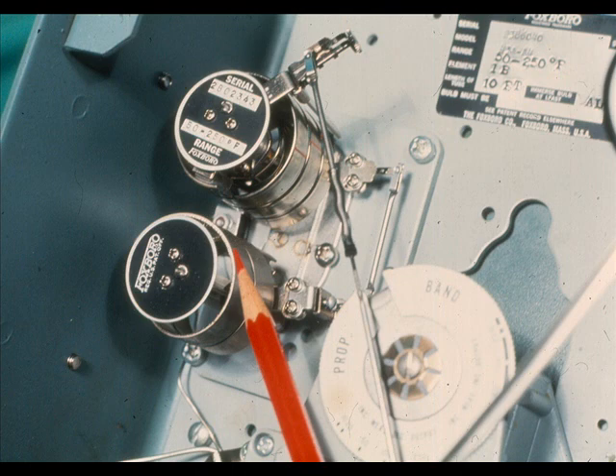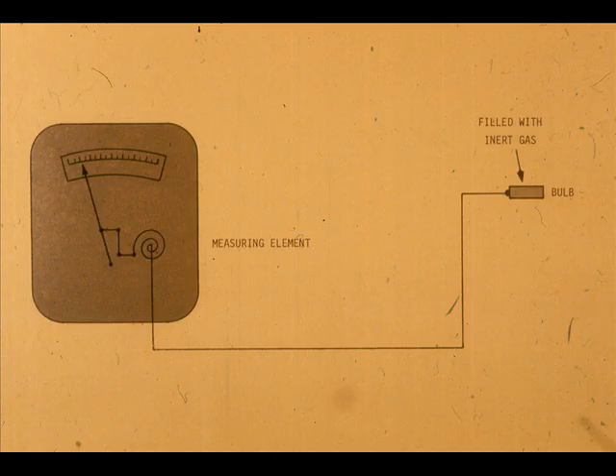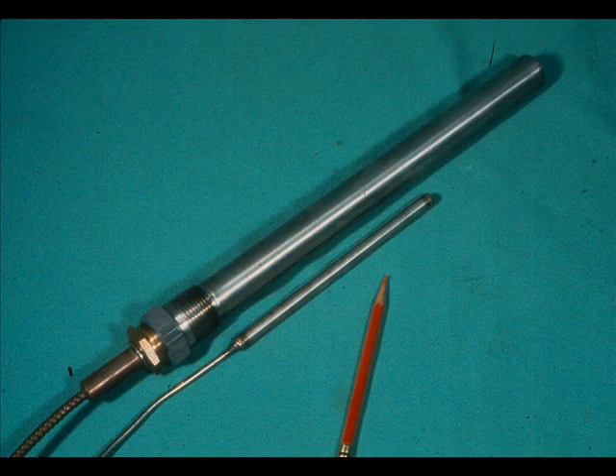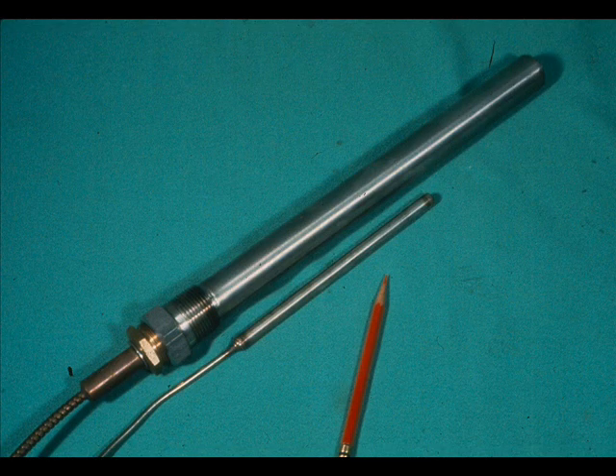The construction of the gas-filled system is almost identical to the liquid-filled system. The major difference is the filling or actuating material. Gas-filled systems use an inert gas such as nitrogen for the operating medium. The gas thermometer bulb is much larger than the liquid type. One reason for this is to make sure the bulb volume is large compared to the volume of the rest of the system.